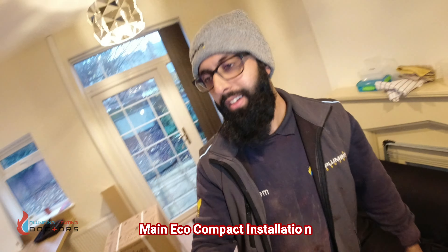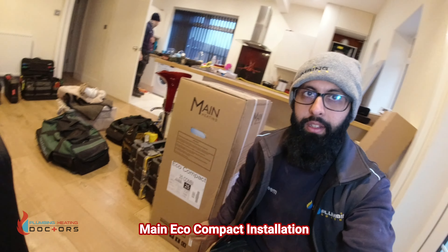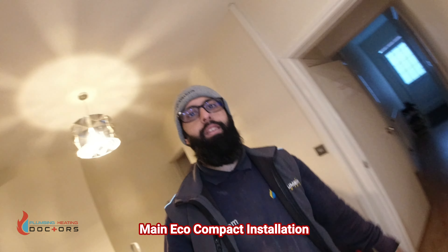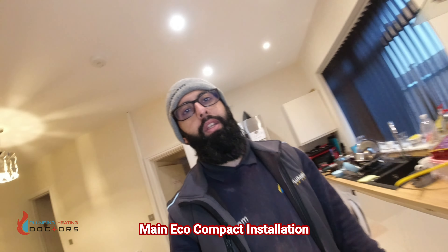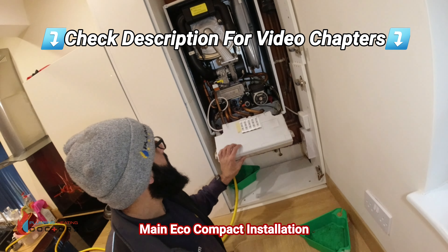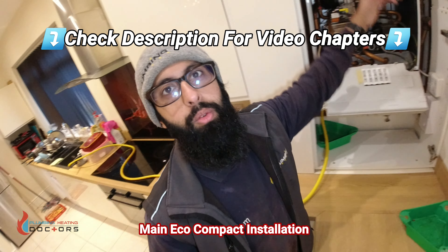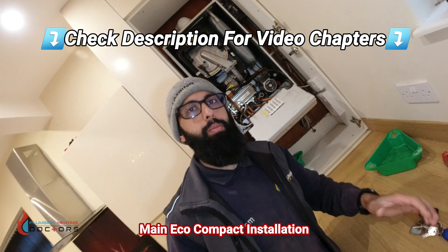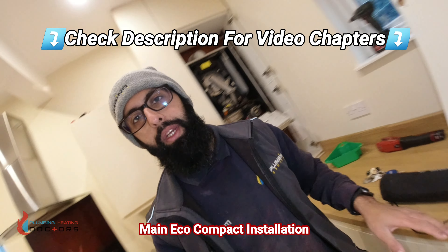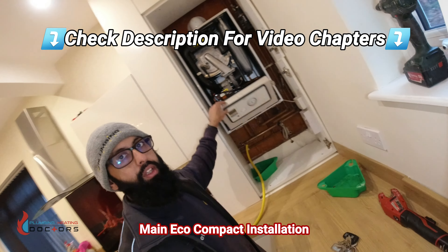So today we're installing this Main Eco Compact boiler. The existing Vaillant boiler has broken down - it needs a new PCB and a new fan. The total repair has come to about £600, so I've advised the landlord that since the boiler is about 10 to 12 years old, it's better to fit a new boiler with a five-year warranty: the Main Eco Compact. It fits in this cupboard nice and easy and it's a lot smaller than the old boiler.